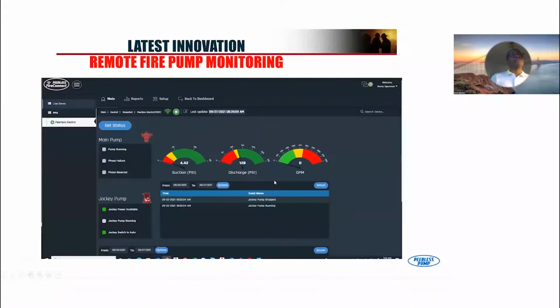So if you look at your app, once you select the site, this is what you'll see: second by second, what your suction pressure is, what your discharge pressure is. Anything green means it's good, you don't need to worry about that. It gives you information about what transpired - when the jockey pump stopped, when it ran, and how long it ran for. You can see it says jockey power available and jockey switch in auto. These are all good indicators that your fire pump is ready to go in case of a fire. It's just right there.